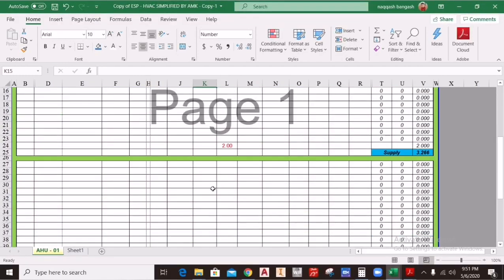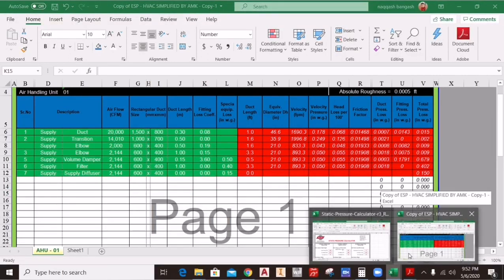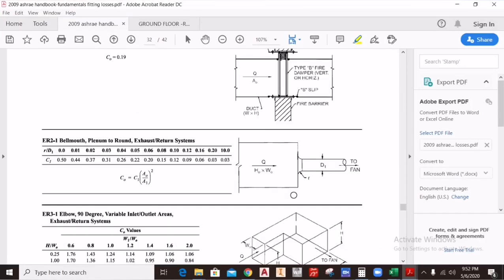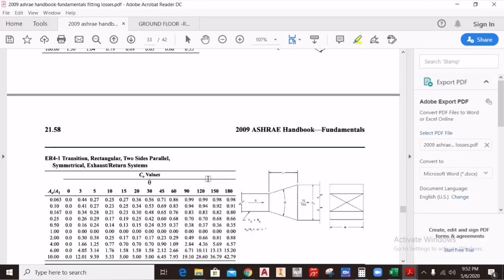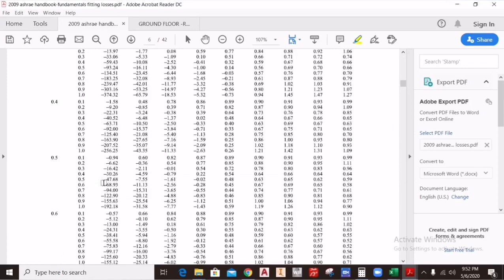Use this method for the supply air duct, return air duct, or exhaust duct as appropriate. If a fan is connected only to the supply air duct and the return is open, you only need to calculate the external static pressure for the supply duct. For an exhaust fan, calculate the ESP for only the exhaust duct — for example, a room with terminals and exhaust duct. The method is the same for all cases, following ASHRAE standards, and applies to both rectangular and round duct fittings.